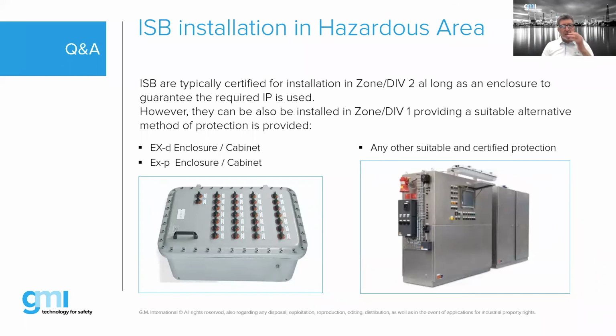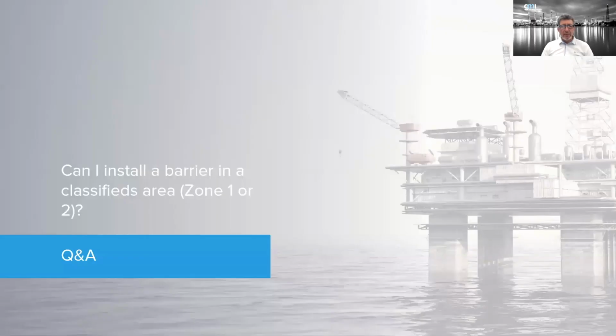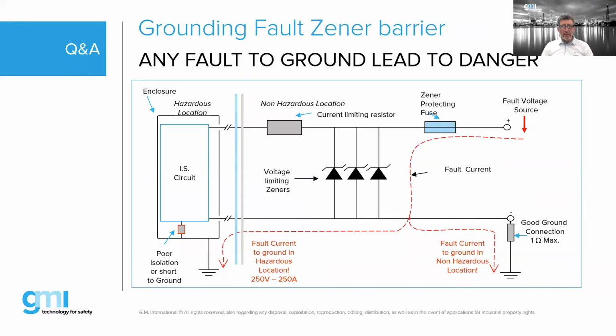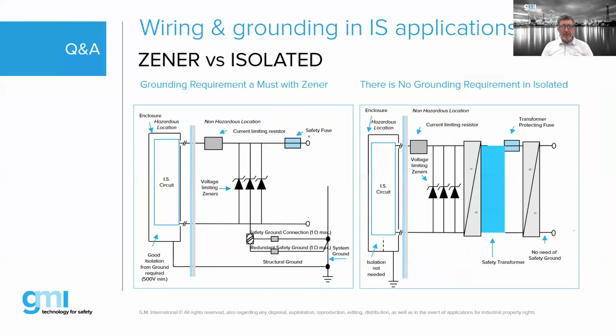Yeah, there's a question. I'm going to see if I can go back to one of the slides here. Either way, there's a live question, Bob, that brings up an interesting point. It says, when we talk about grounding of Zener barrier, does that mean grounding of the barrier body or grounding of signal screens from the field? That's a good question, because screens have a special requirement for grounding in Zener barrier.